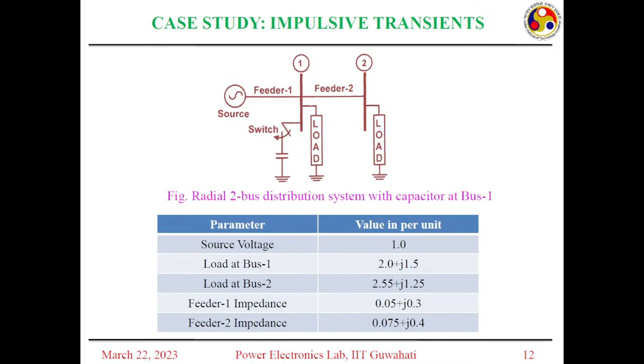Now, let us say at load 1 I have connected a capacitor, and I will do the same step. So there is a capacitor at bus 1. Instead of a sudden increase, there is an oscillatory transient here. You can see there is the same impulse at the source, but the bus 1 voltage is oscillating and it is settling within 1 cycle. Similarly, the bus 2 voltage also has oscillations.